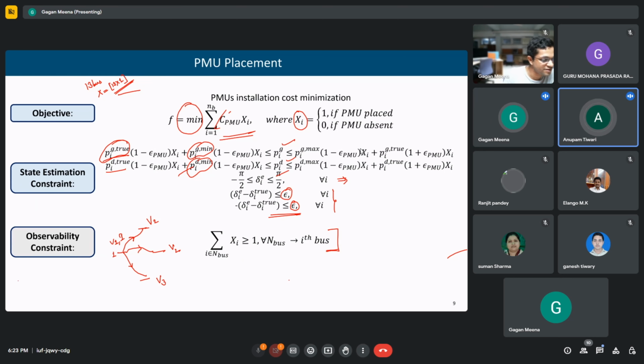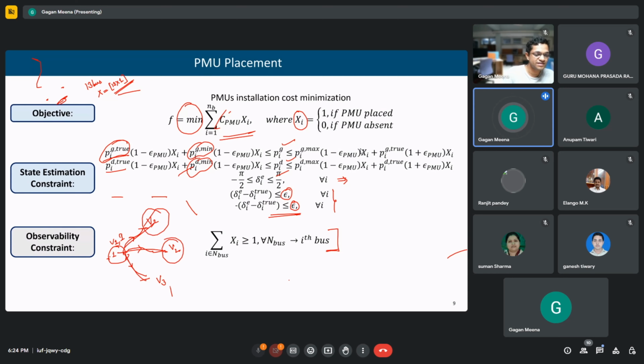In this example, my bus 1 is connected to 3 buses, it is a direct connection, so I can calculate the voltage of the other buses. But in a situation where it is not connected directly, observability will not be possible, so for that we need more PMUs. One relation coming out of this is that direct connection is a must for observability, because since this bus is connected to other buses, if we have a PMU at this bus, we can measure and calculate parameters at these three buses also.